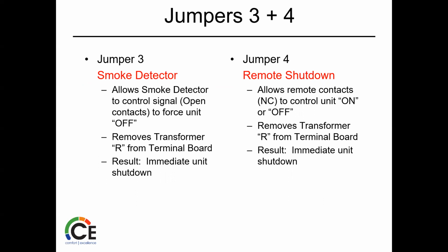Takes power from R because that's right in that initial 24-volt path. So if that's open, excuse me, you're not going to see power between R and C on your terminal strip because it already cut it before it even got there. And that's the last spot that the transformer power hits. So it runs through all of this stuff first. Same for remote shutdown. It's going to immediately terminate shutdown.